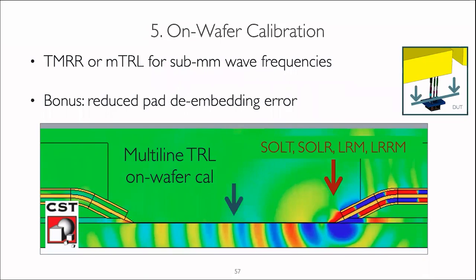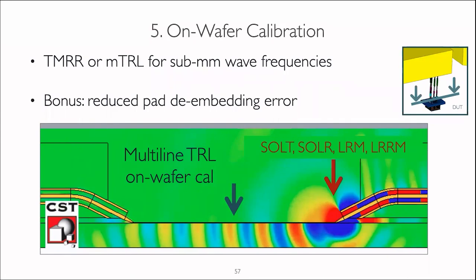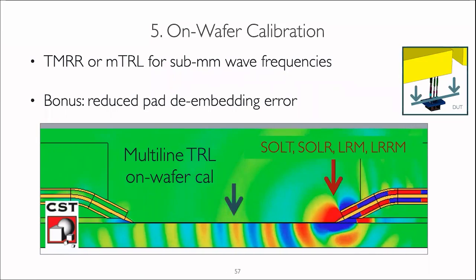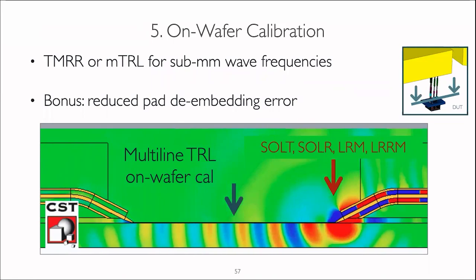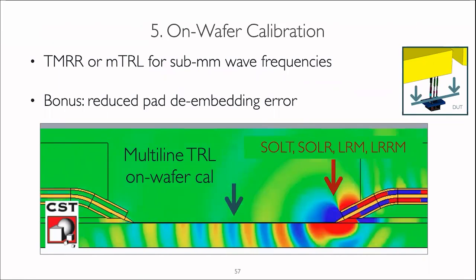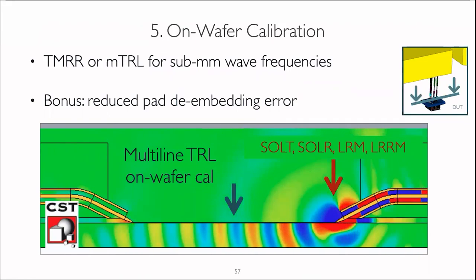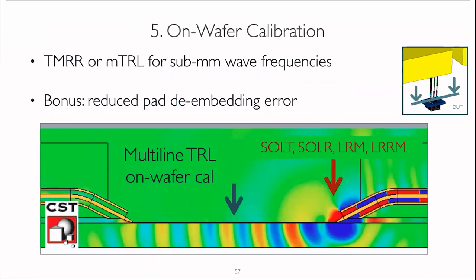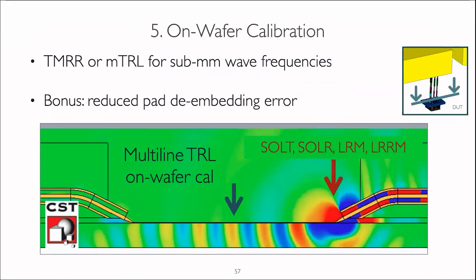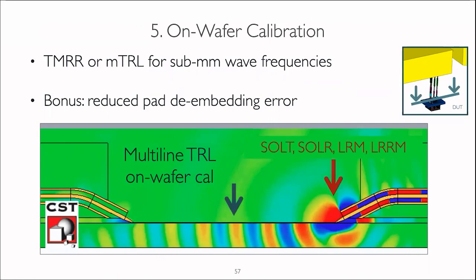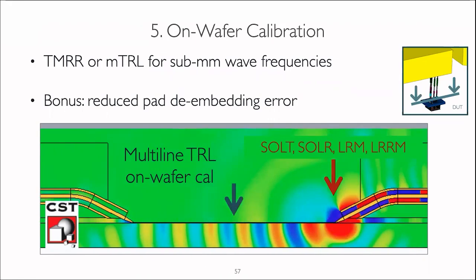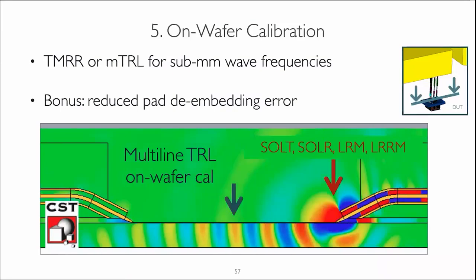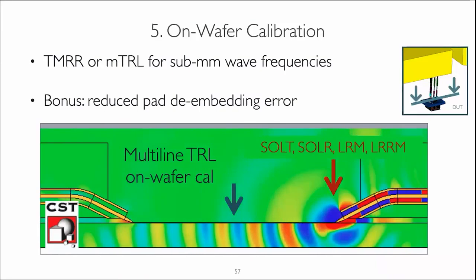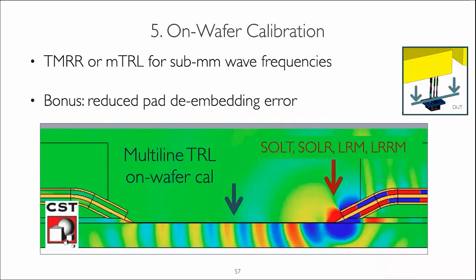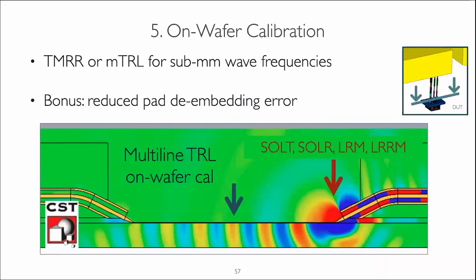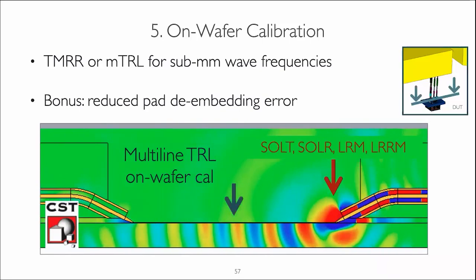The possible solution for this problem is to use standards which are located far away from the transition point, which means that SOLT, SOLR, and LRM methods are probably not desired when using probe tip calibration standards at millimeter wave frequencies. So either use offset calibration standards, or the always better way is to go directly to on-wafer calibration standards, where your probe and transition point are far away from the physical location of the standard, and the standards are very close to the device and the test terminals. The bonus of this approach is that you get rid of the parasitics of your device and the test infrastructure.